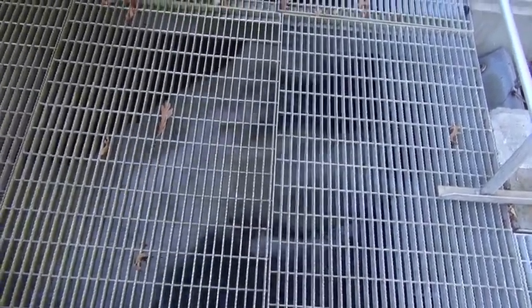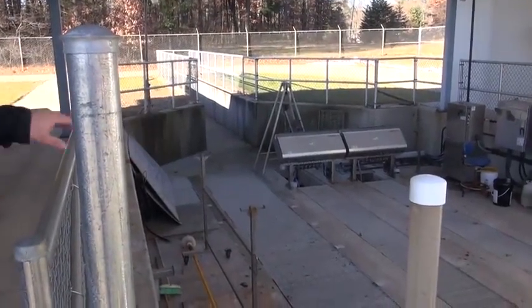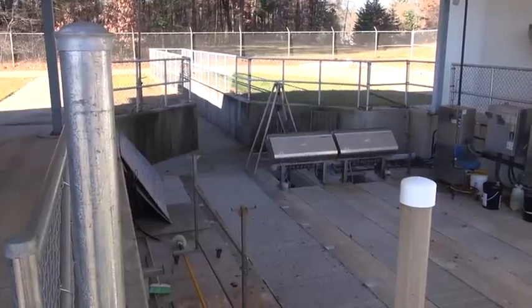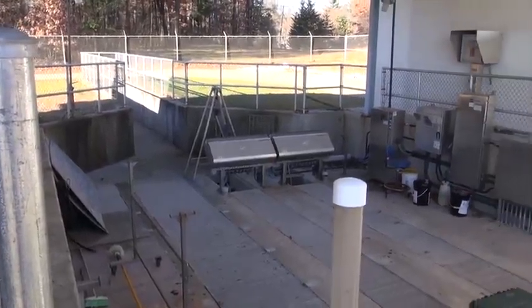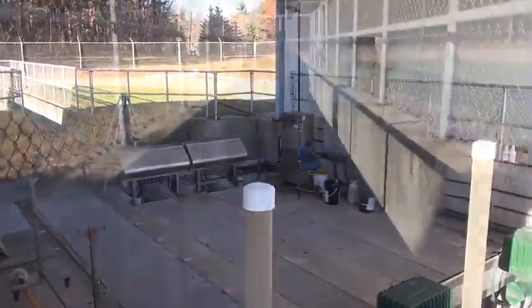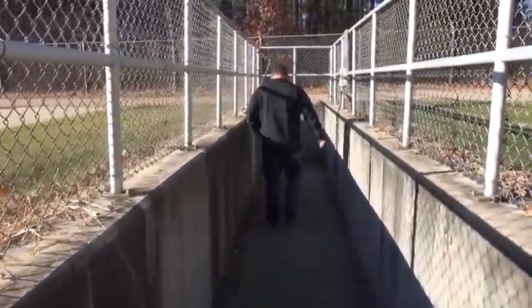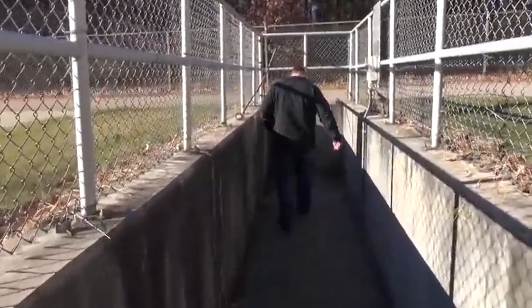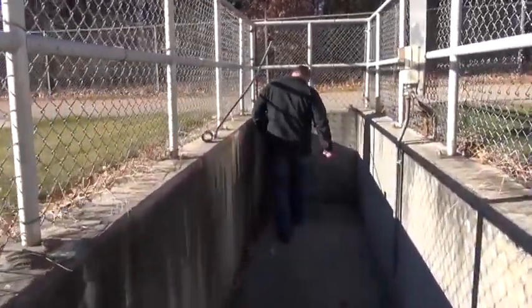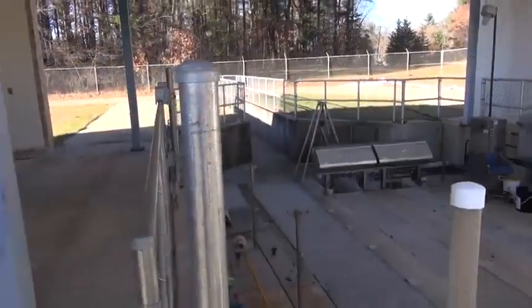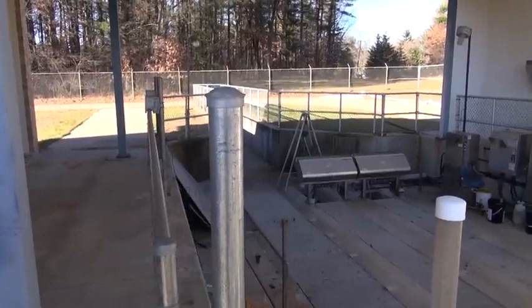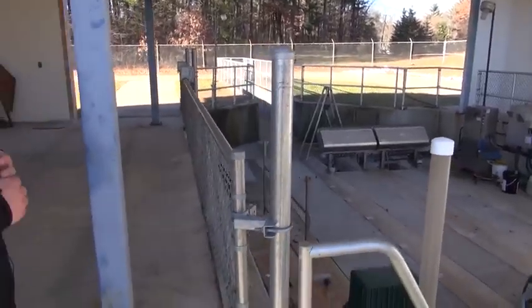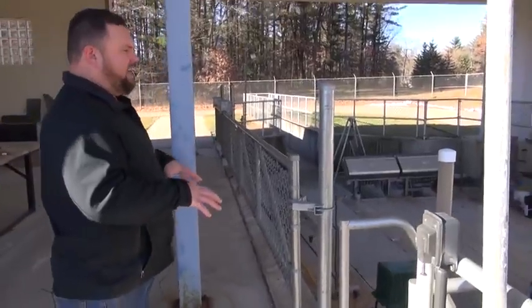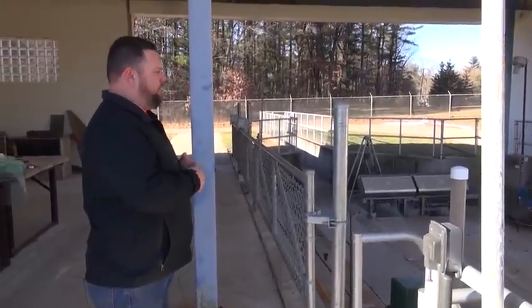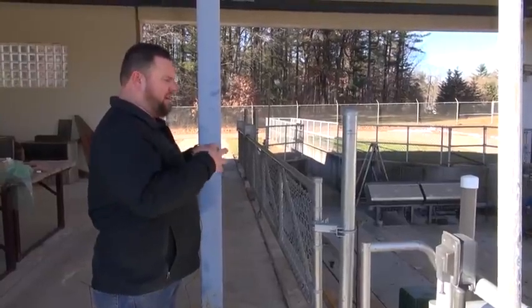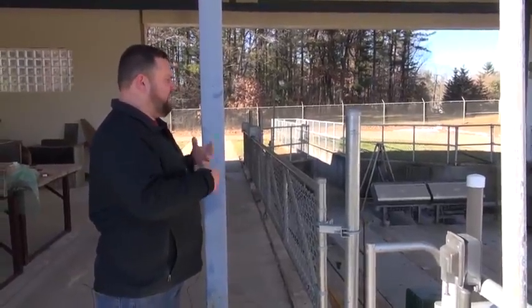So basically, those 4 stainless steel cabinets that you see, and then the control panels over there, are the UV disinfection system. And underneath the grates in those channels would be where the bulbs are sitting in the water. So we're controlling them from all those different points where they're connected to the actual control modules, and they're ramping the light up or down based on the transmittance in the water. So if it's nice, good, clean, clear water, the UV system's going to ramp way down. If we're having a little bit of issue or we're having some turbidity in our effluent, it's going to ramp the UV system up, and we're going to get a better kill on the bacteria that might be moving through the system.